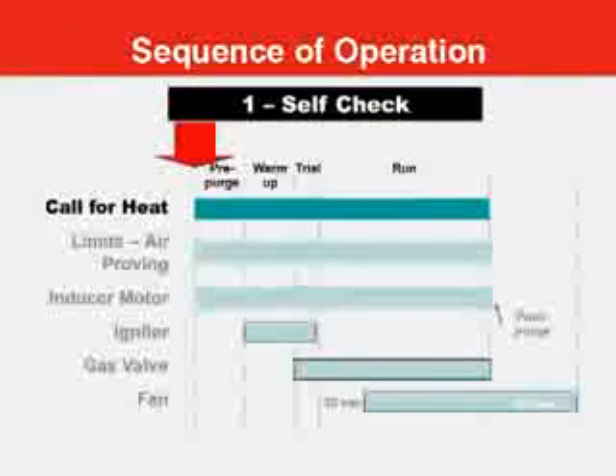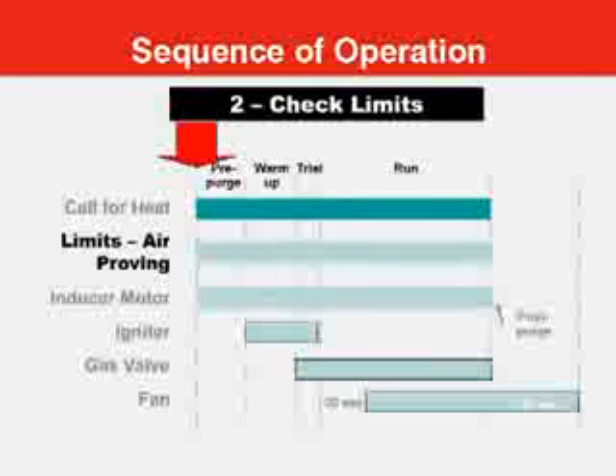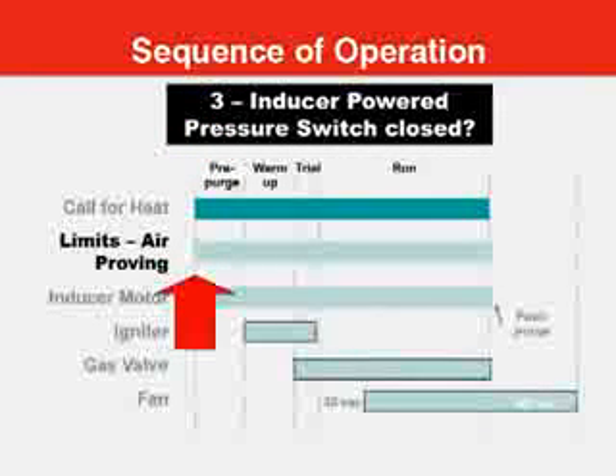Here's a sequence of operation graphic. We'll go through it step by step. First, on a call for heat, the control does a self-check to make sure it's working okay and is ready to start the burner. Then it checks to see that the limit switch is closed, that the rollout switches are closed, and the air-proving pressure switch is open. If that all checks out, the inducer motor is powered up and the control starts looking to see if the pressure switch closes, proving airflow.